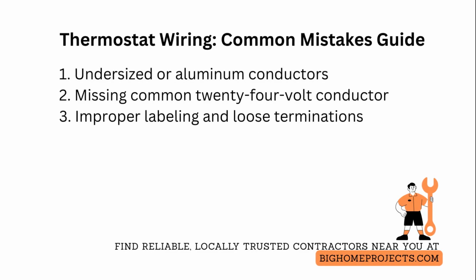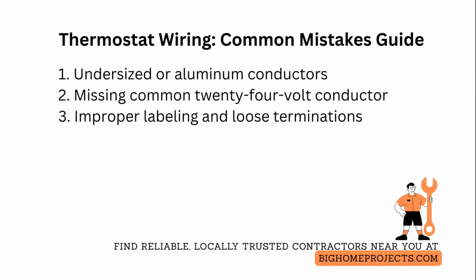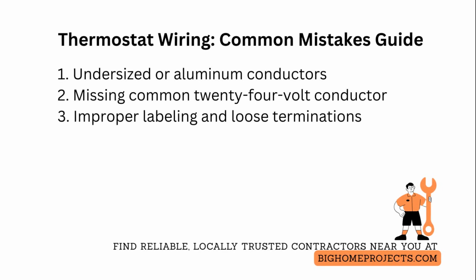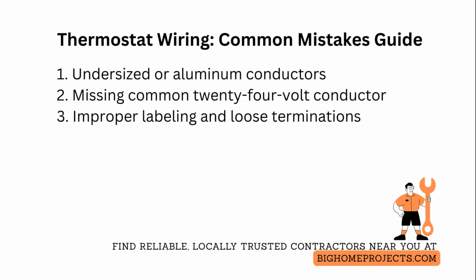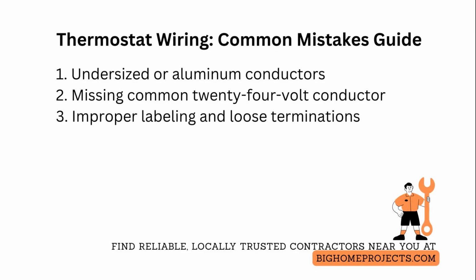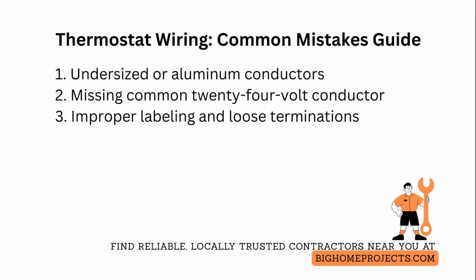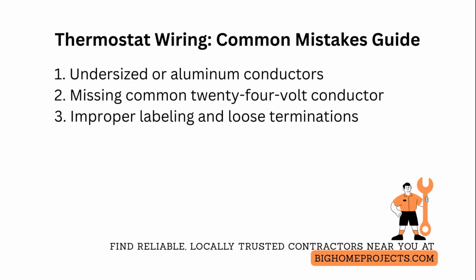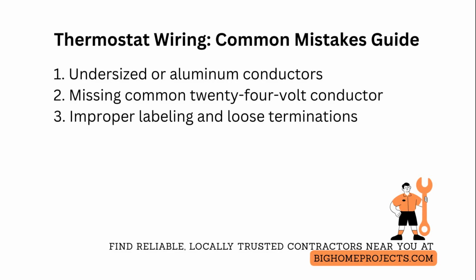One of the biggest thermostat wiring mistakes is using undersized wire or aluminum conductors, which causes voltage drop and poor control response. Fix this by running copper 18-gauge or larger as specified and redoing any suspect runs. One of the next common errors is skipping the common 24-volt conductor for smart thermostats, resulting in frequent dead batteries or reboot loops. Fix by running a 6-conductor 18-gauge cable or installing a common adapter or an additional transformer.